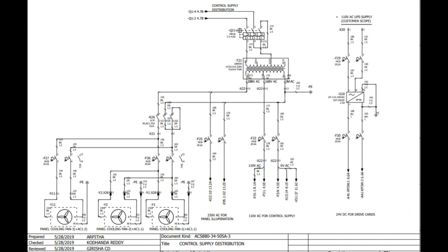In this slide, we will discuss the tapping we have seen in the previous slide. The tapping is given for control supply distribution Q21. Just for reference, you can turn to the previous slide and you can see there is a tapping which we haven't discussed in the previous page, that is Q21. So it will contain 415 volt, two phases of the three phase supply, and there is an MPCB. Once we switch it on, it will feed the transformer, that is control transformer, 1 kVA the rating of the transformer, and the output of the transformer is of two different voltages. One is 110 volt and another is 230 volts. So first we'll discuss the 110 volt. This will feed F22 MCB, and that we will use for control supply.